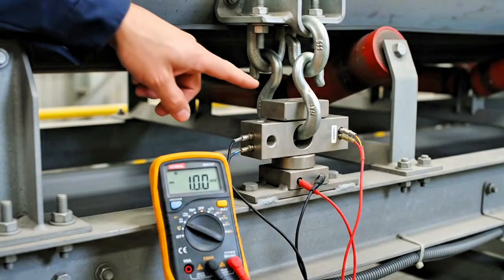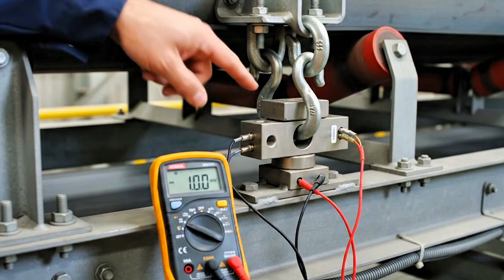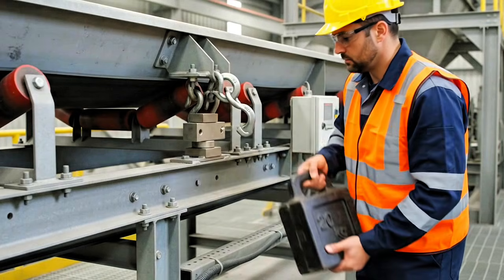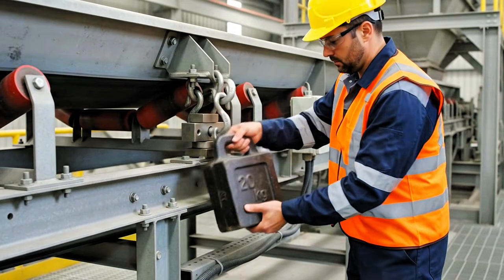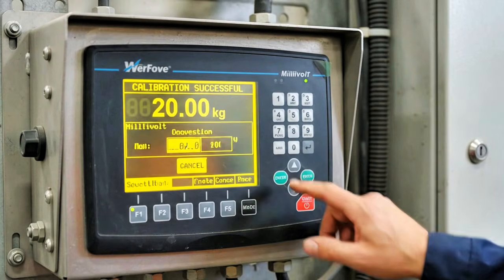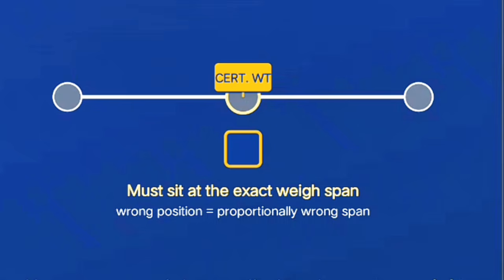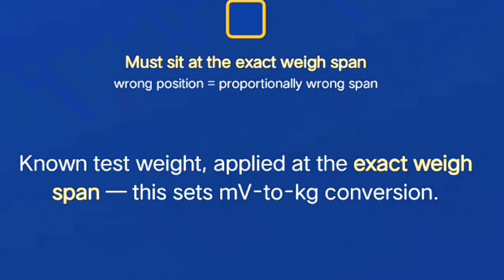Span calibration: this is where you apply a known, certified test weight directly onto the weigh idler, or use calibrated test weights hung from a calibration frame if your feeder has one built in. You enter the test weight value into the controller, it reads the load cell response, and calculates the span factor, essentially, the conversion between millivolts and kilograms for that specific installation.